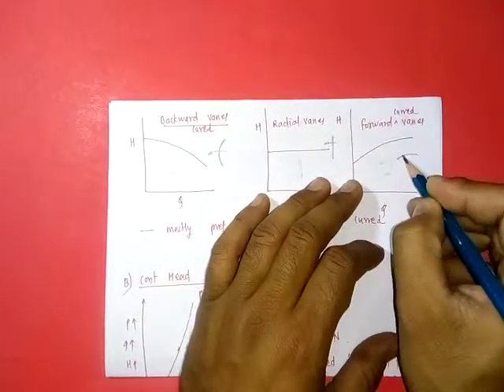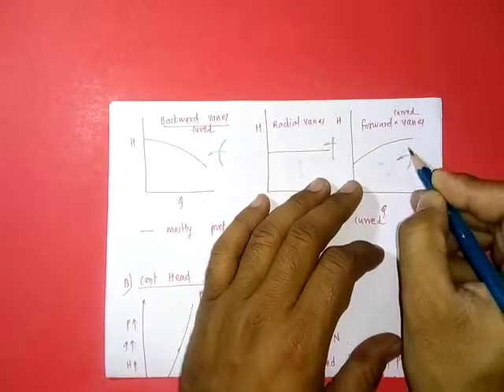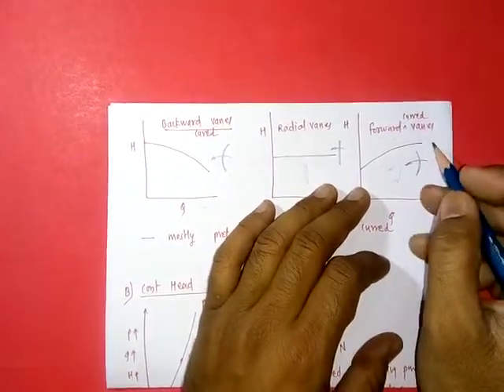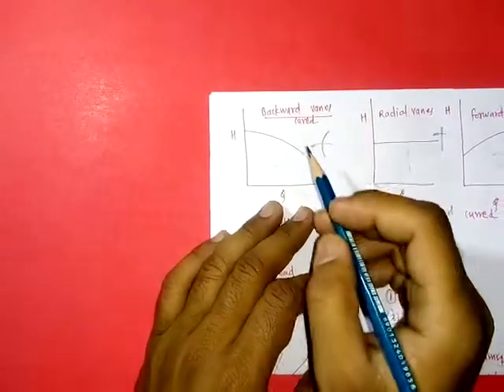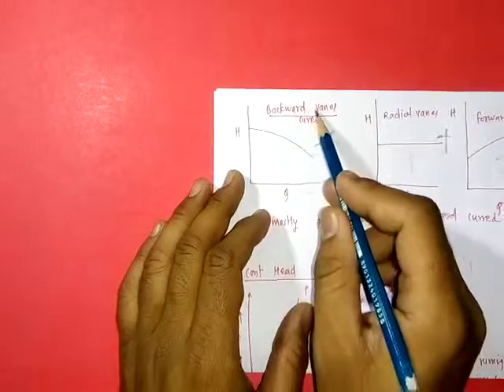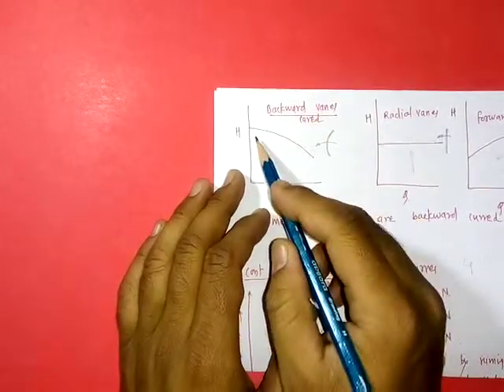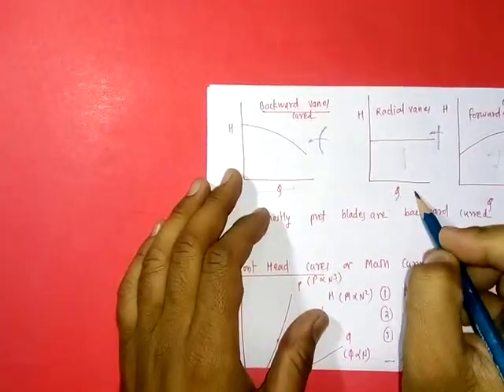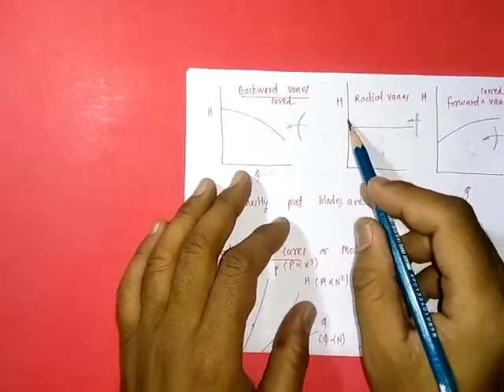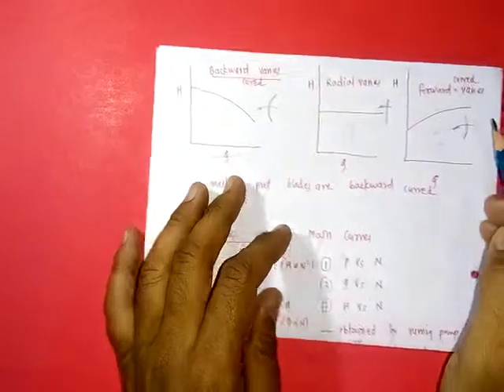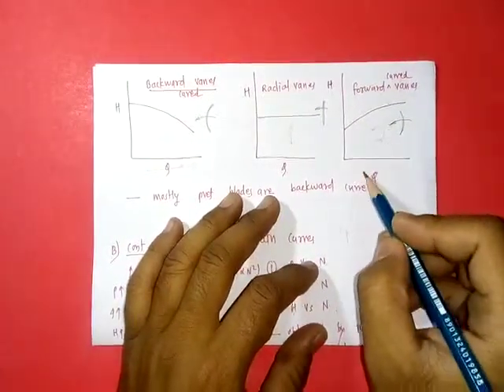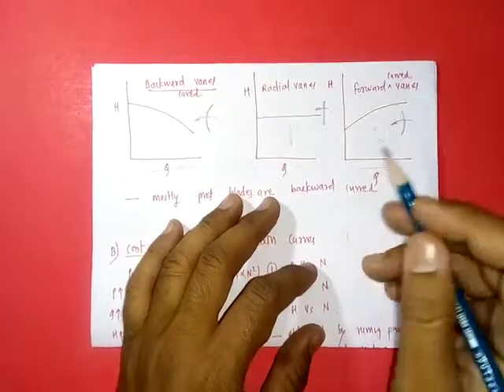Third is forward curved vanes — if this is the direction of rotation, the vanes are curved in the forward direction. For backward curved vane pumps, as discharge increases, head decreases. For radial vanes, with increasing discharge, head remains constant. For forward curved vanes, as discharge increases, head also increases.